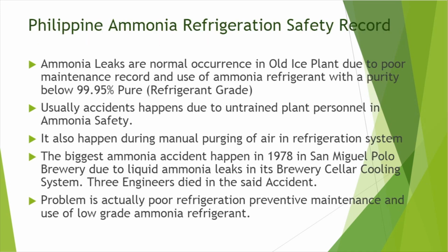Ammonia leaks are a normal occurrence in old ice plants due to poor maintenance records and the use of ammonia refrigerant with a purity below 99.95% or refrigerant grade. Usual accidents happen due to plant personnel untrained in ammonia safety. It also happens during the manual purging of air in the refrigeration system, as they don't use an automatic purger.